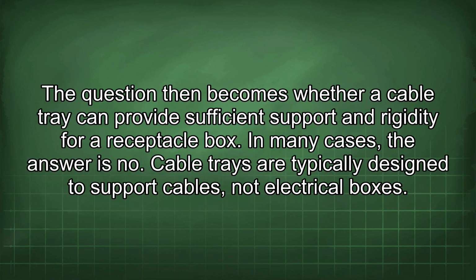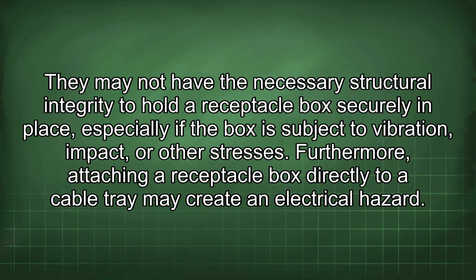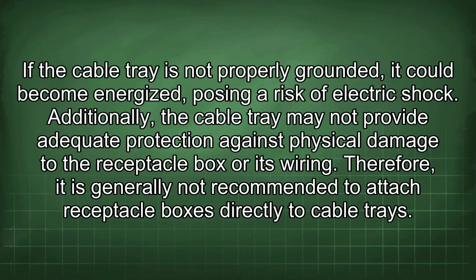The question then becomes whether a cable tray can provide sufficient support and rigidity for a receptacle box. In many cases, the answer is no. Cable trays are typically designed to support cables, not electrical boxes. They may not have the necessary structural integrity to hold a receptacle box securely in place, especially if the box is subject to vibration, impact, or other stresses. Furthermore, attaching a receptacle box directly to a cable tray may create an electrical hazard. If the cable tray is not properly grounded, it could become energized, posing a risk of electric shock. Additionally, the cable tray may not provide adequate protection against physical damage to the receptacle box or its wiring.